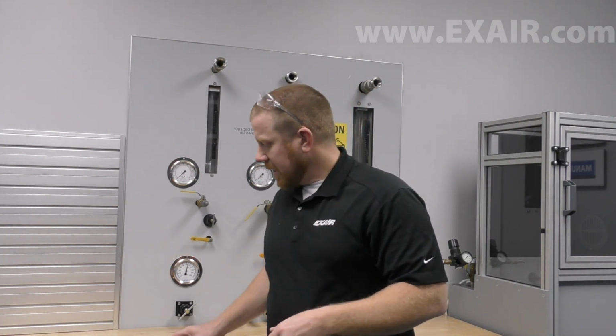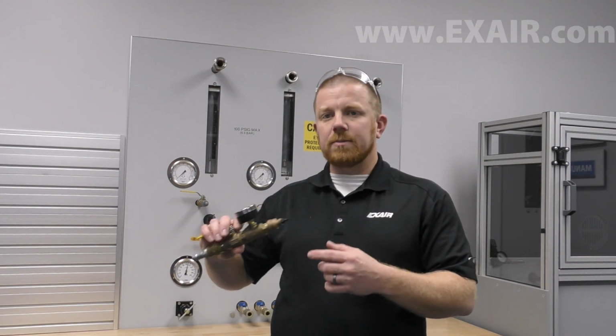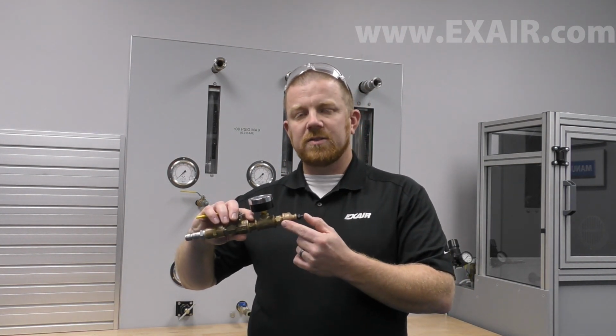So whether you're setting up a test or if you're going to be using one of these to monitor performance in an everyday process, the easiest way to do that is to place a pipe T right on the inlet to the device, and then place your pressure gauge right there at the inlet to the process.